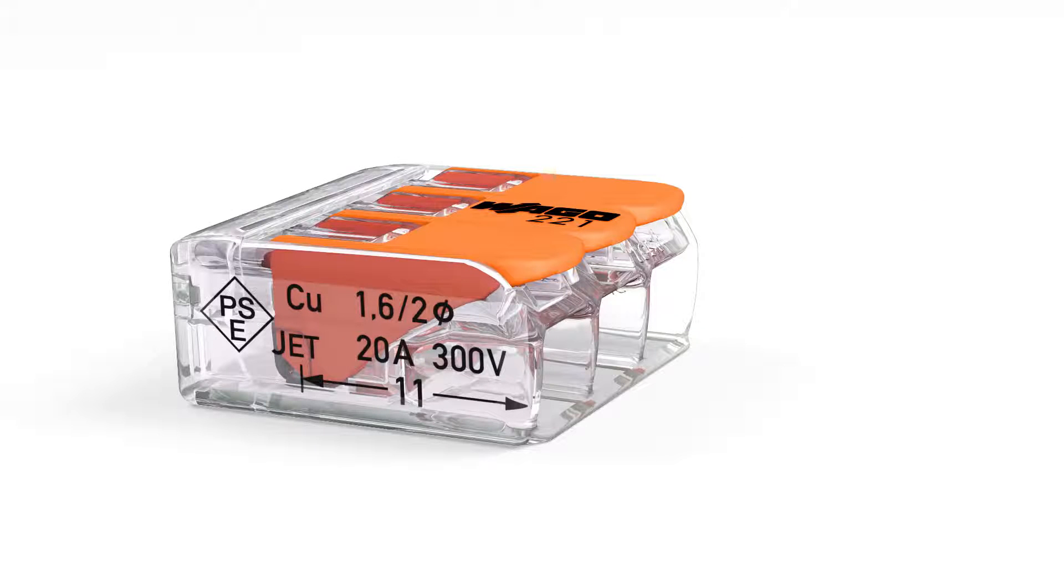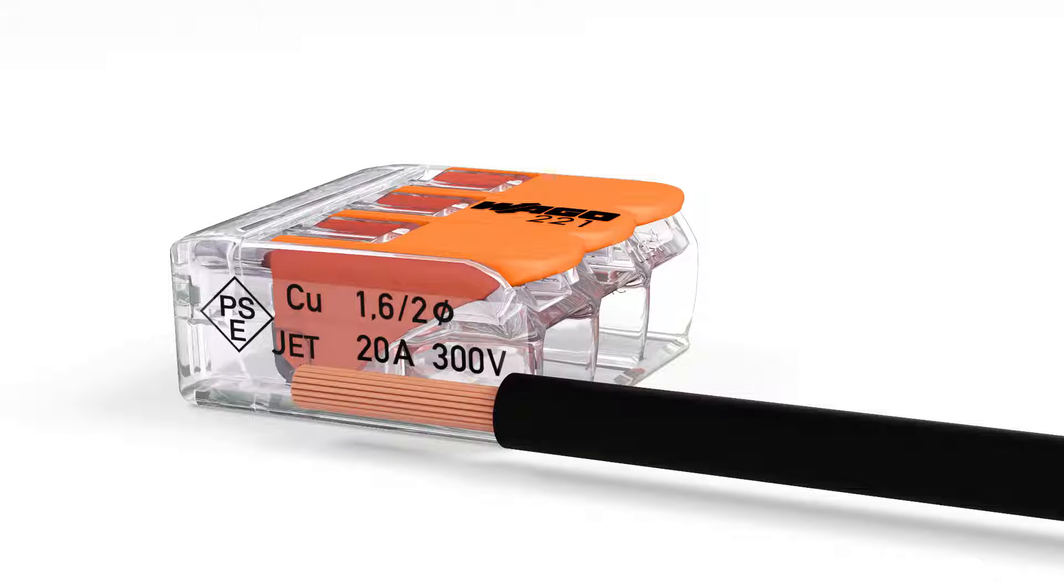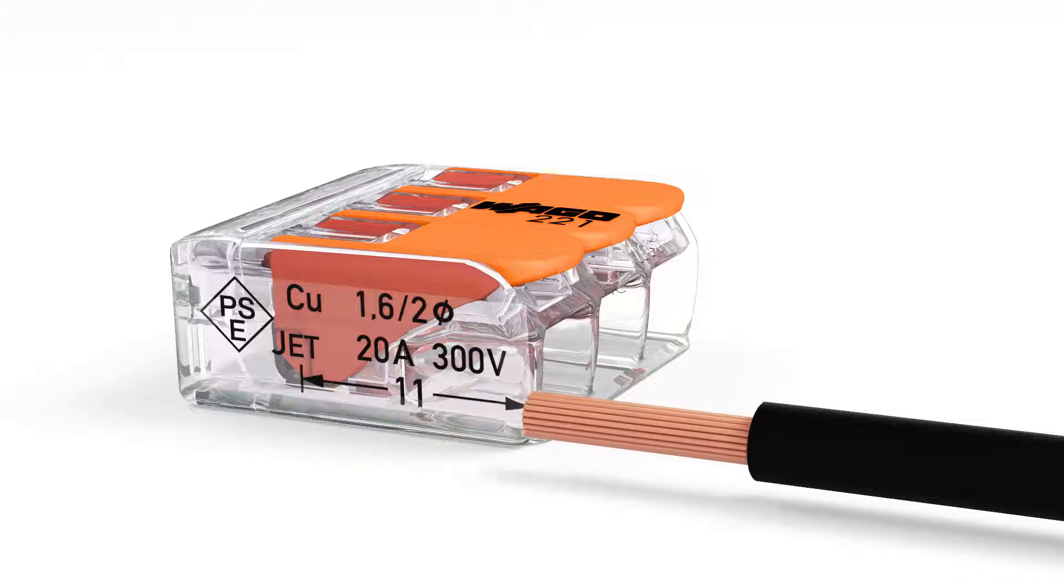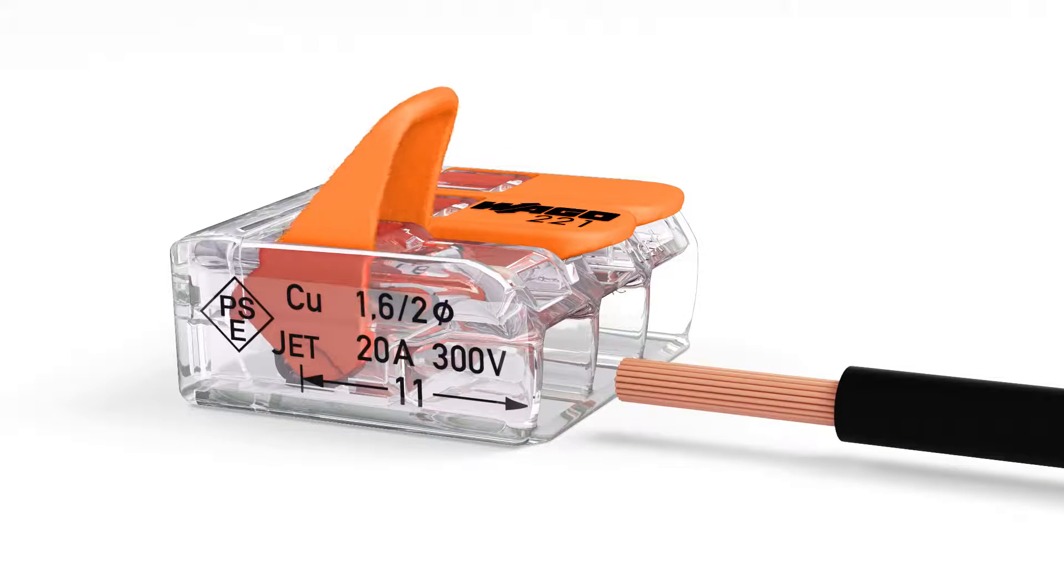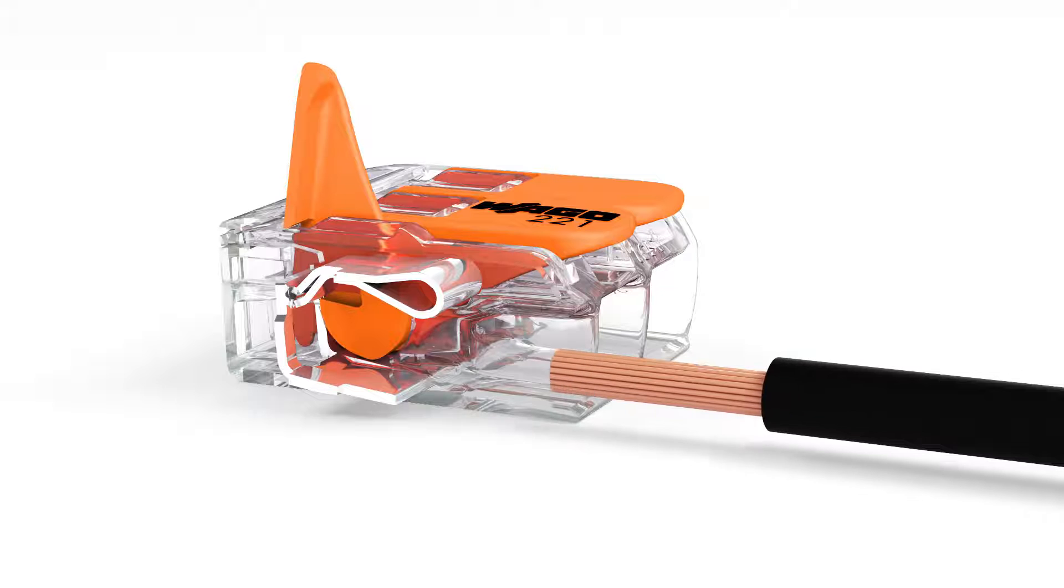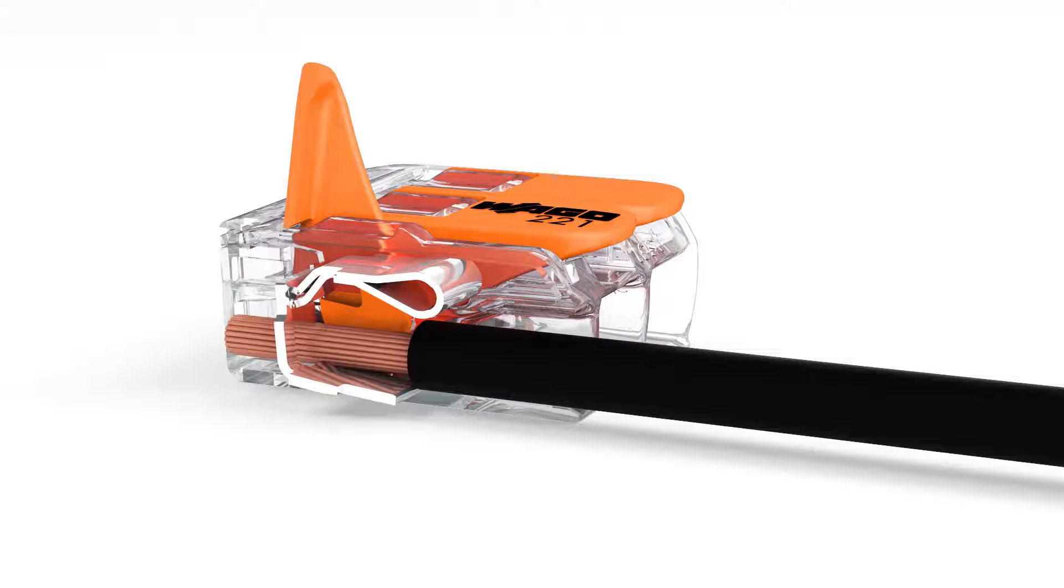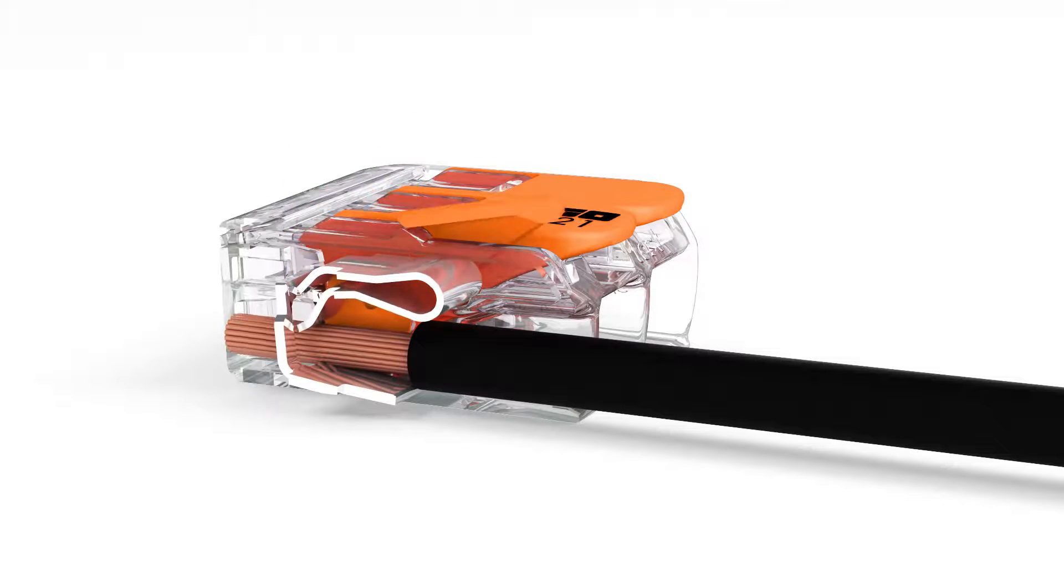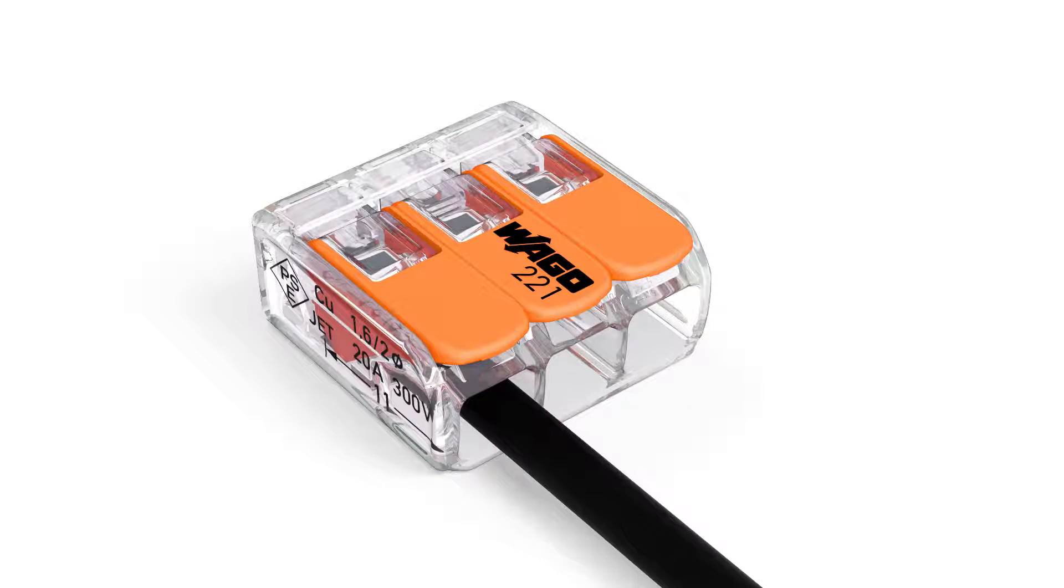Wiring is very easy. Strip conductor to 11 millimeters or 0.43 inches. Open the clamping unit via integrated lever. Insert conductor. Compared to its predecessor, the 222 series, the 221 series operating levers can now be opened using noticeably less force. Then lower the lever to close the clamp.